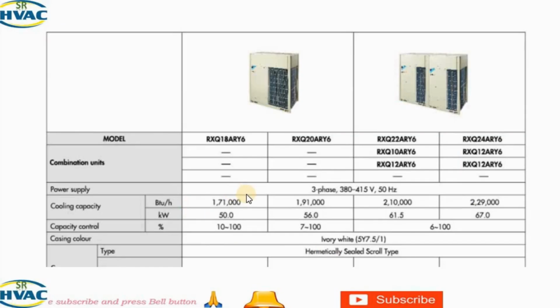Daikin VRV electrical system. First will be our basic power supply. The outdoor unit required a 3-phase power supply with proper voltage and frequency, as per Daikin specification. Always check the unit nameplate related to the voltage, frequency and the current capacity. Use MCB current rated to protect the circuit. Ensure cable size is correct to handle the current without overheat, and proper ground connection must be made to prevent electrical hazard.